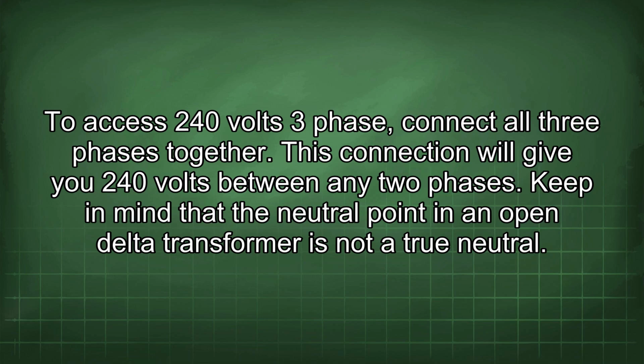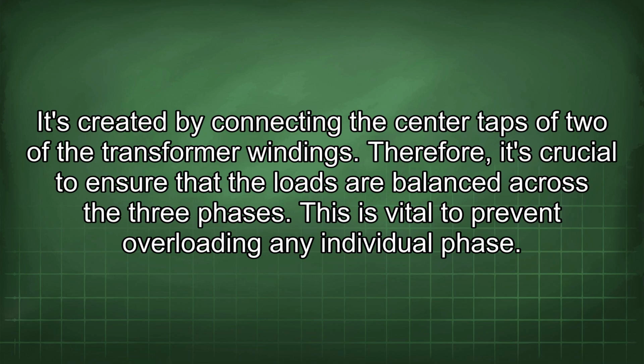Keep in mind that the neutral point in an open delta transformer is not a true neutral. It's created by connecting the center taps of two of the transformer windings. Therefore, it's crucial to ensure that the loads are balanced across the three phases. This is vital to prevent overloading any individual phase.